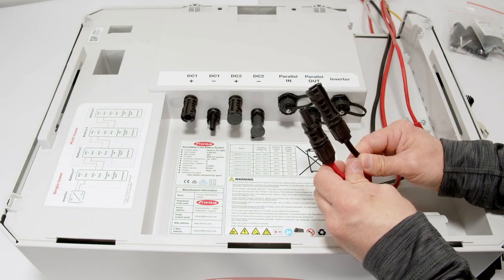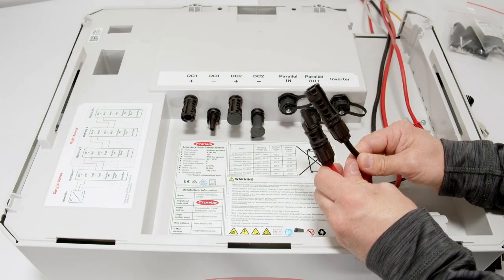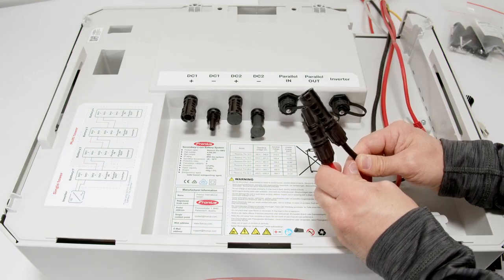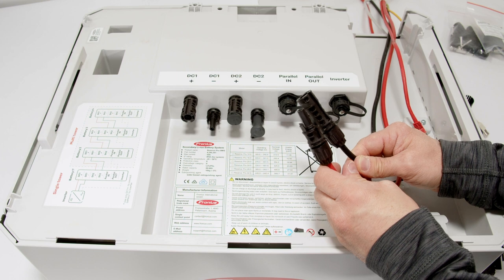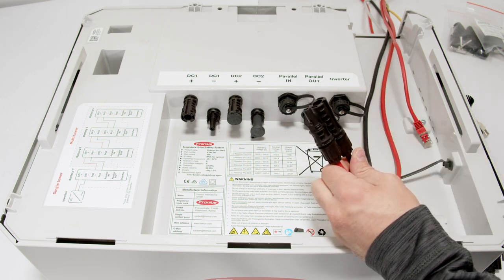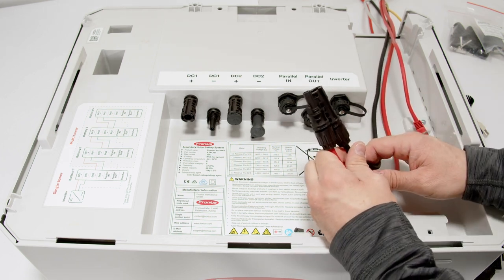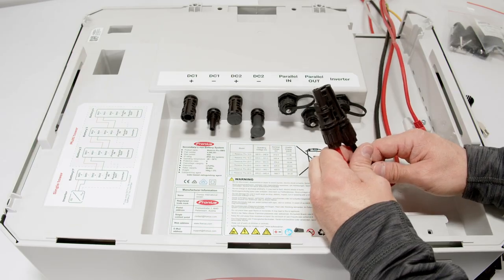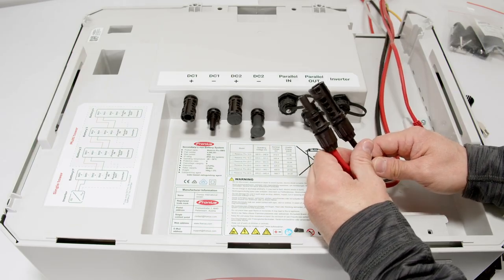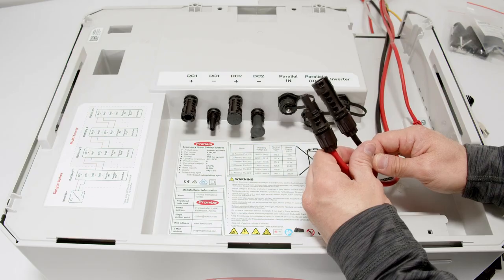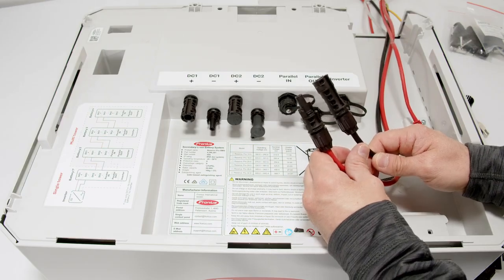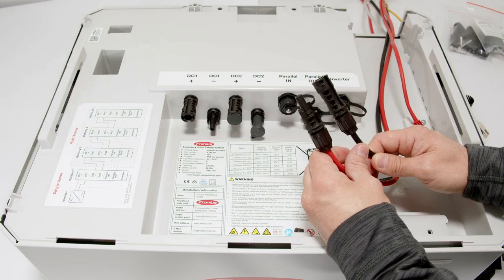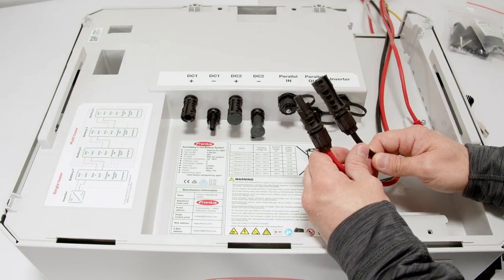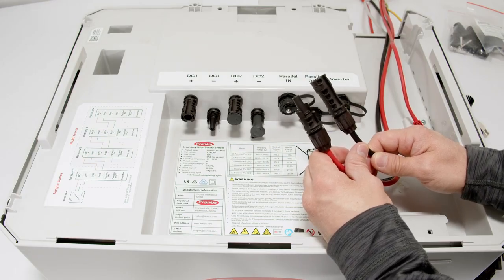Please note very carefully, depending on which inverter you are using, so either the Gen 24 Plus or the Verto Plus, which cable you are using. Since the 6 square millimeter cables are good up to 47 amps and the 10 square millimeter cables are good for up to a maximum current of 62 amps. So normally this would mean that for the Gen 24 Plus devices, you can take the 6 square millimeter cables and the plugs, and for the Verto Plus, you need to take at least the 10 square millimeter cables and the plugs.